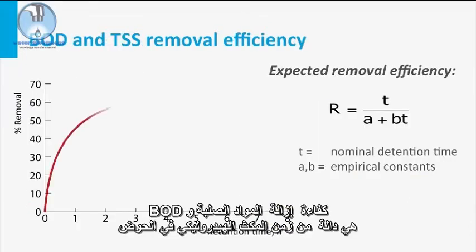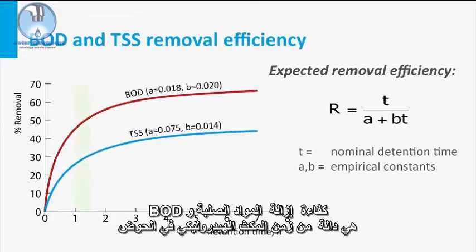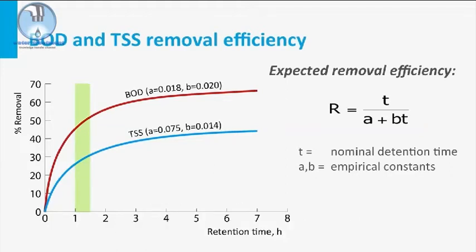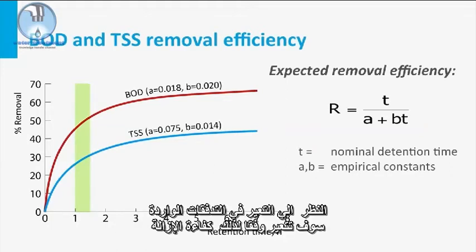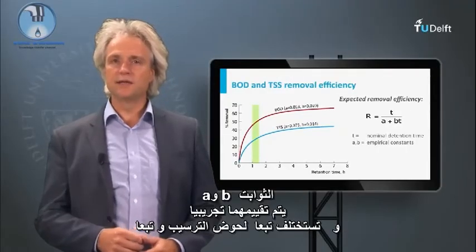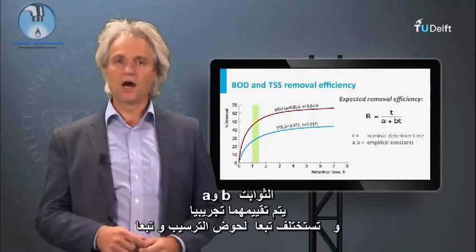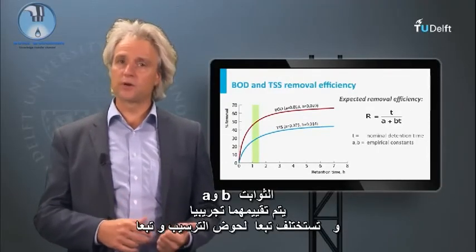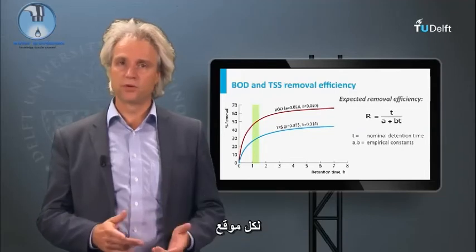The solids and BOD removal efficiency is a function of the applied hydraulic retention time in the tank. Considering the fluctuating incoming flows, removal efficiency will accordingly fluctuate when the duration of the peaks exceeds the design HRT. The shown constants A and B are empirically assessed and will differ per clarifier and per location.